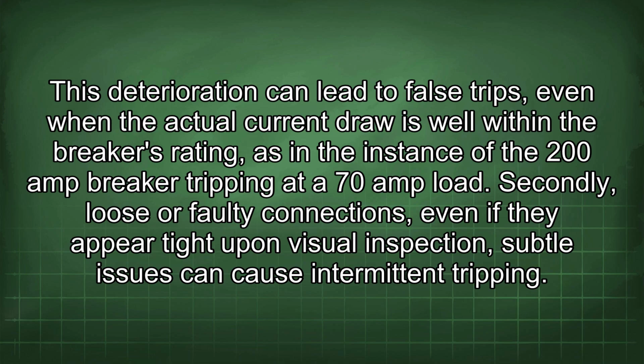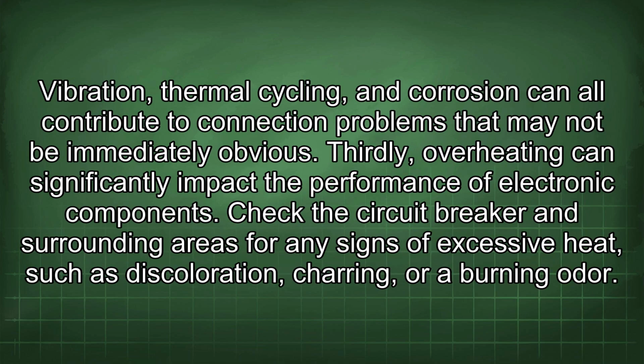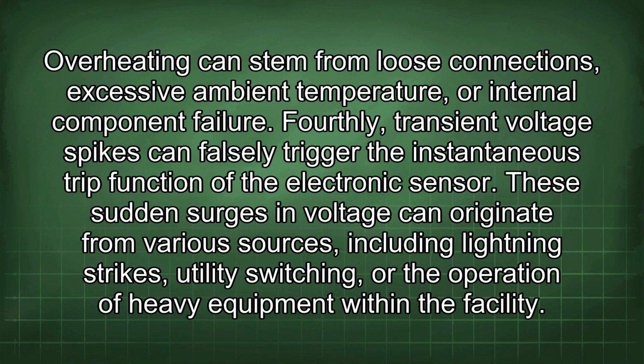Secondly, loose or faulty connections. Even if they appear tight upon visual inspection, subtle issues can cause intermittent tripping. Vibration, thermal cycling, and corrosion can all contribute to connection problems that may not be immediately obvious. Thirdly, overheating can significantly impact the performance of electronic components. Check the circuit breaker and surrounding areas for any signs of excessive heat, such as discoloration, charring, or a burning odor. Overheating can stem from loose connections, excessive ambient temperature, or internal component failure.